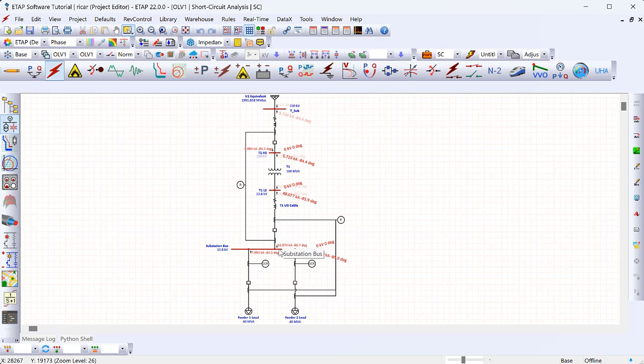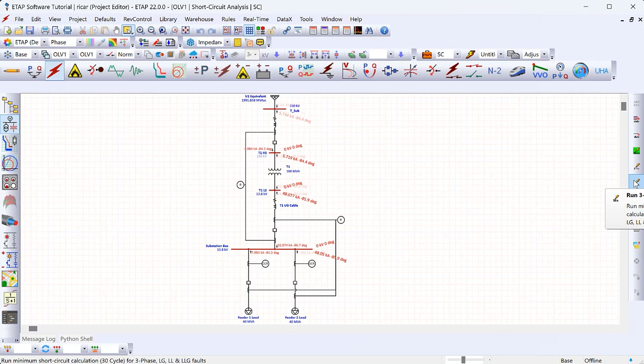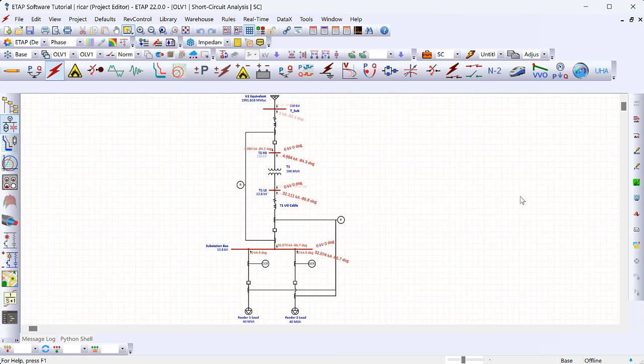During the first few cycles of a fault, motors will back-feed into the fault, but that subsides with time. Clicking 'Minimum' runs a 30-cycle short circuit, showing fault current levels 30 cycles after the fault — this removes contribution from induction motors and uses the synchronous reactance for any synchronous generators. It's essentially a steady-state fault current level after all transients have decayed.